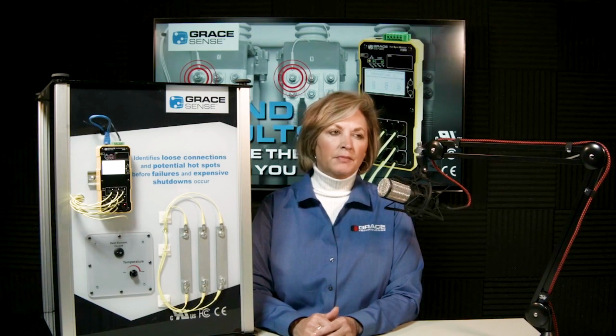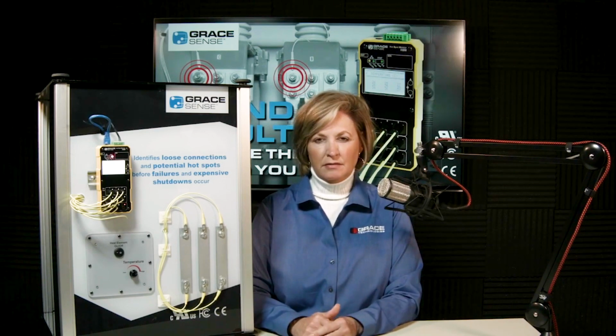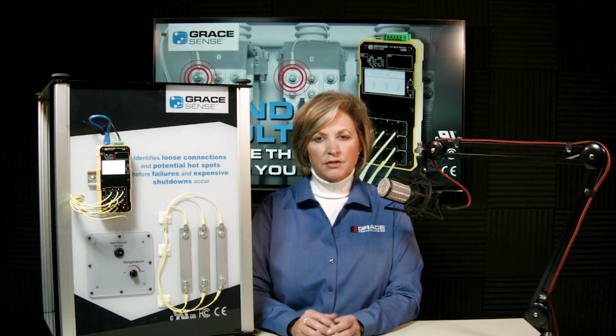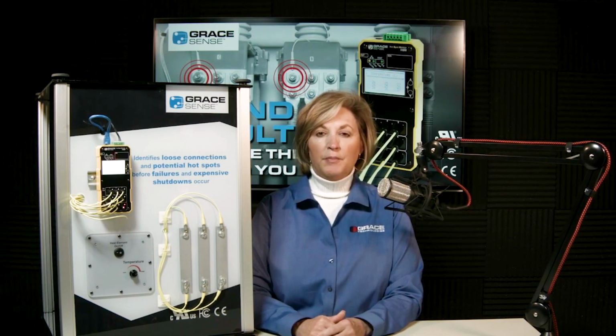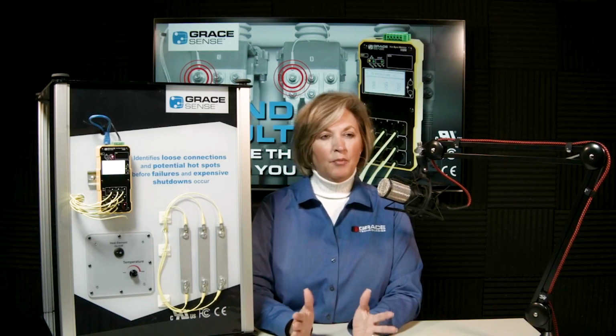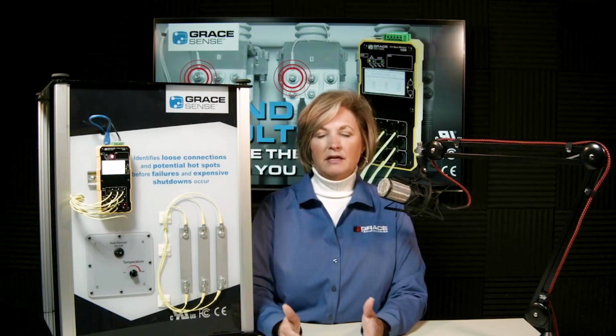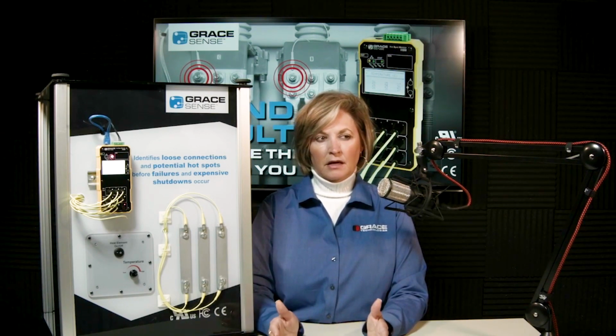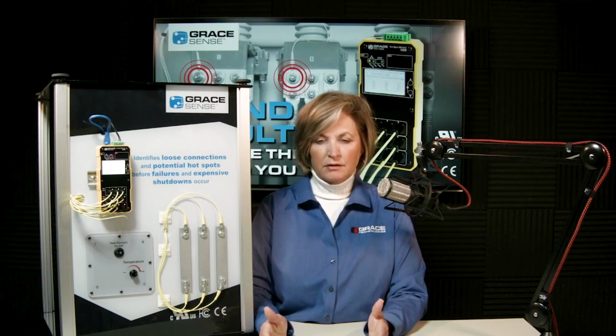We always like to get medium voltage drives. That is a completely different story. There are hundreds and hundreds of voltage connections in medium voltage drives. One way we like to really look at it is those points which are either hidden or have the potential to get hot. So we do look at those. There are probably upwards of 36 points per medium voltage drive, depending on who manufactures it. That would be a very interesting point to obtain. We call it a point of interest too.